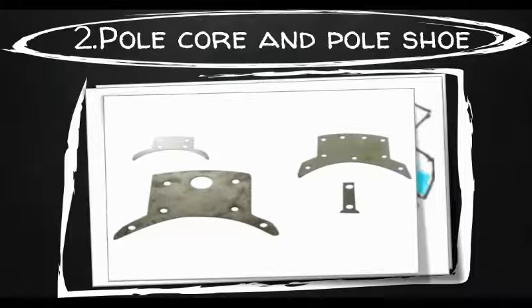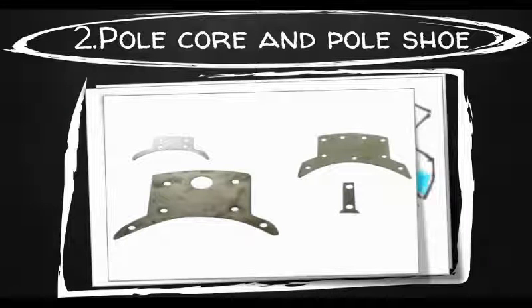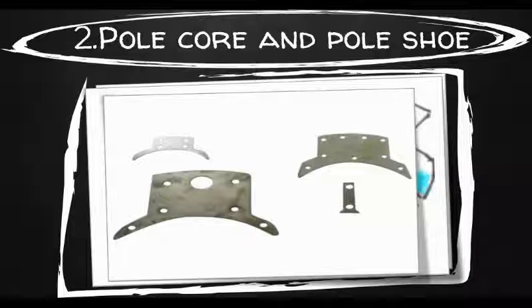There are two types of pole construction. First, the pole core itself may be of solid piece made up of either cast iron or cast steel, but the pole shoe is laminated and is fastened to the pole face by means of countersunk screws, as you can see in the figure. In the modern design, the complete pole core and pole shoes are built up of thin laminations of annealed steel which are riveted together under hydraulic pressure.